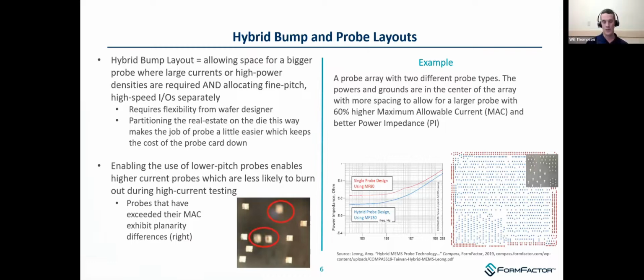Back on this slide: probe burnout is a real problem, especially during high current testing. Some products might get tested at 10 times the current of their actual use case. What often happens is that the probe and test might be designed for that 10x, but a faulty die, depending on how it's faulty, might cause a short and draw even higher current than that 10x you allowed for. So in that case, you really want the largest pitch probe you can use, or a wider probe with space between them to allow for higher power.